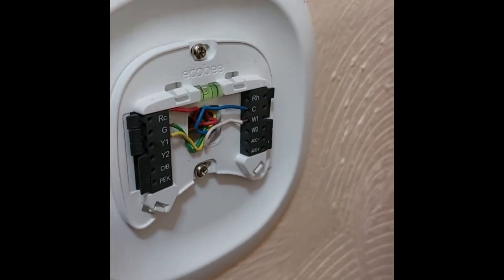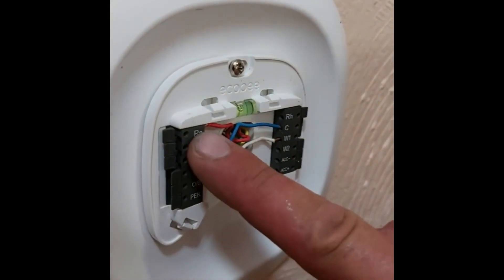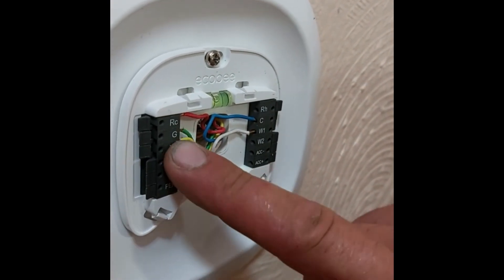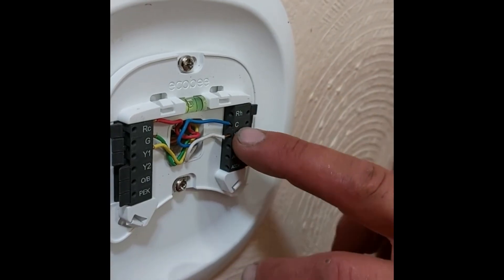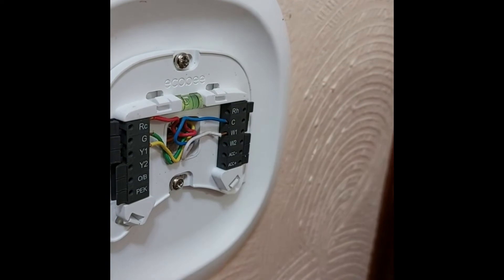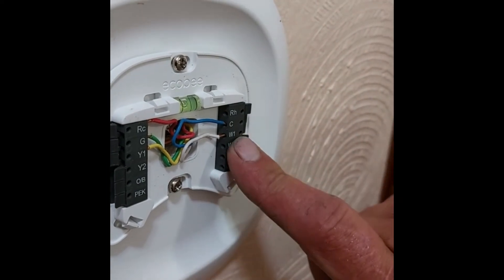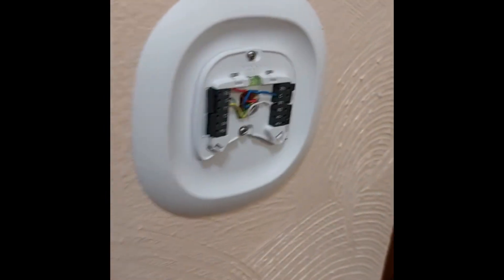The technician walks through each wire: red is your constant power; green is your fan; yellow is your cooling; blue is your common wire, which runs a 24-volt current circuit or connection circuit; and white is your heating, which turns your furnace on and off. On a heat pump you would also have an O or B wire.